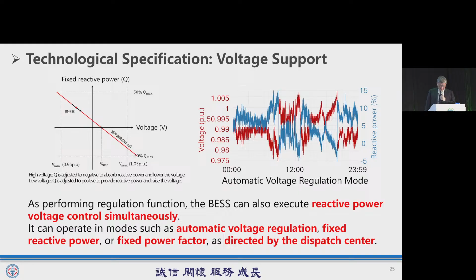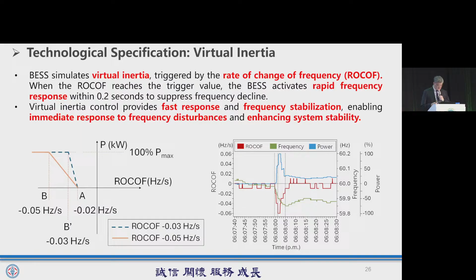BESS can also simulate something called virtual inertia. When the system detects a rapid change in frequency, measured by ROCOF, it can trigger a fast response in under 0.2 seconds. That means the battery immediately responds to inject or absorb power and slow down the frequency drop. This kind of fast response behavior is especially important now that we have fewer traditional generators providing natural inertia. Virtual inertia from BESS helps fill the gap and makes the grid more stable during sudden disturbances.